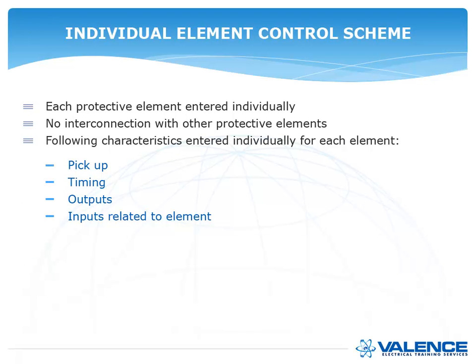When you have an individual element control scheme, each protective element is entered individually. There's no interaction with other protective elements, so that makes it very simple to understand, operate, and program. So you normally set up the pickup, timing, outputs, and whatever inputs are related to the element. So you can block it with an input if you want, such as a loss of potential or something like that.